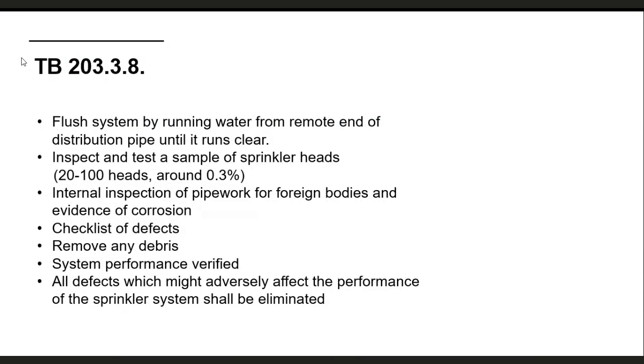That will depend on the type of building you've got and how you want to conduct these tests. If you're an industrial building - and the technical bulletins are often written from an industrial or commercial point of view - say you've got a warehouse, you can decide to turn off all the sprinklers for two weeks, drain it all down, and do this 25-year inspection thoroughly. Take your time, do a good job, then turn it all back on when finished. With other buildings, that may not be so easy.